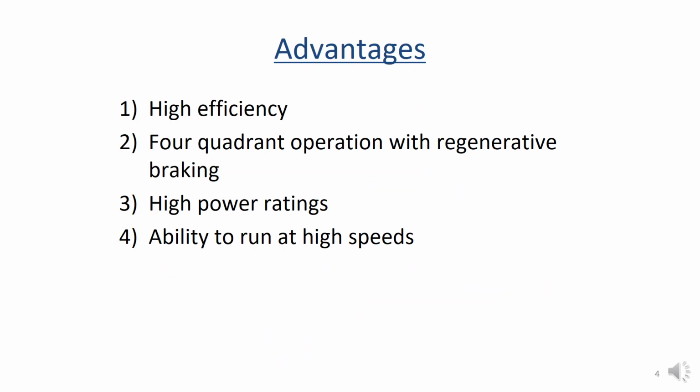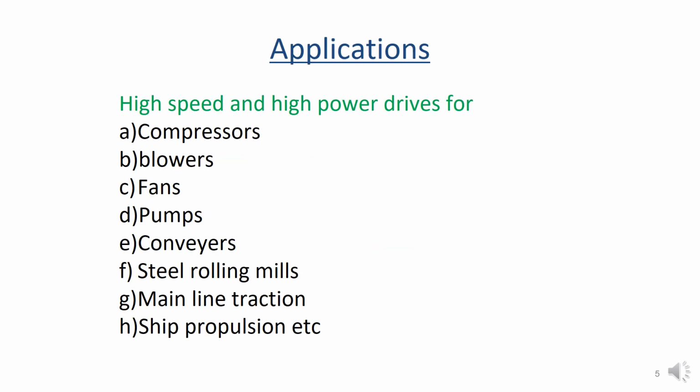See the advantages of this synchronous motor drive. First, it has high efficiency. Then four-quadrant operation is possible, so regenerative braking is possible. It has higher power ratings and also the ability to run at high speeds. The applications of synchronous motor drives are high speed and high power drives for compressors, blowers, fans, pumps, conveyors, steel rolling mills, mainline traction, ship propulsion, etc.